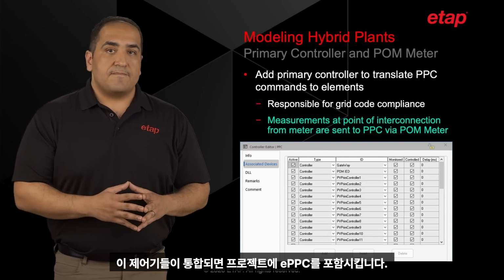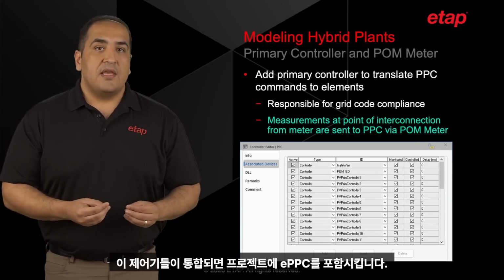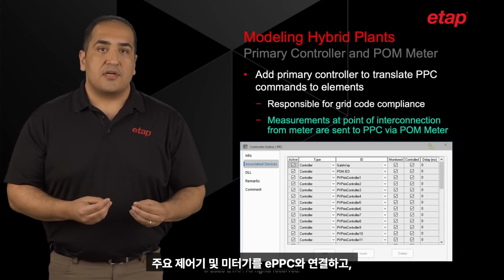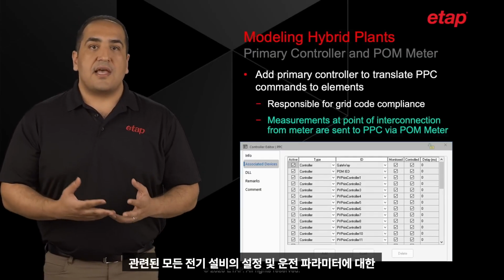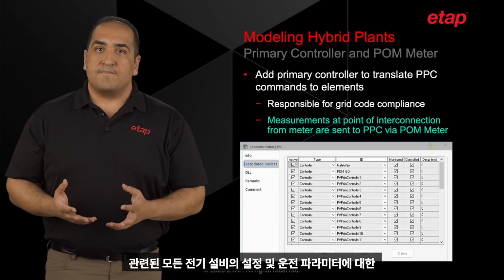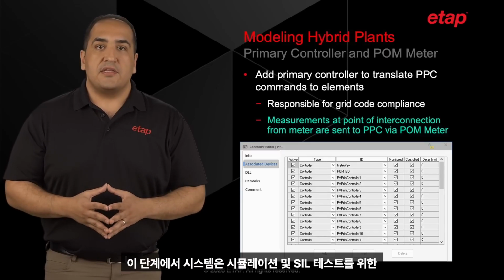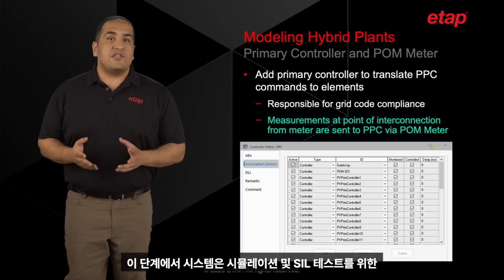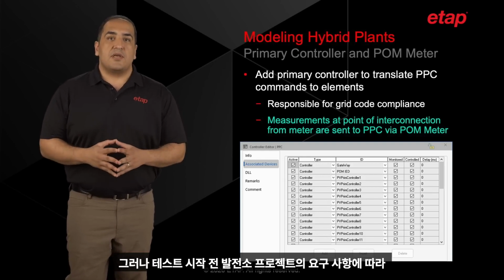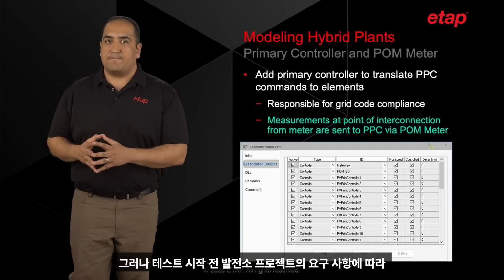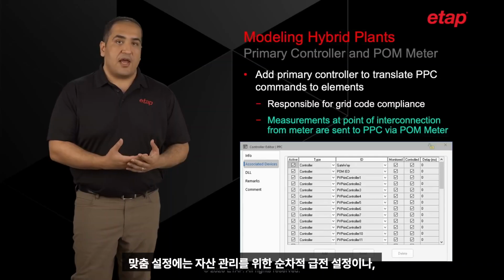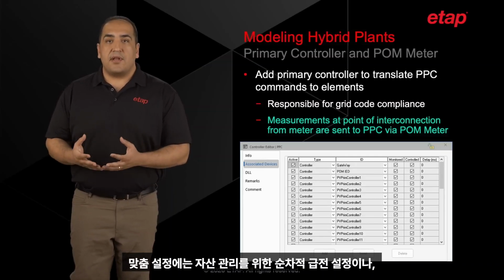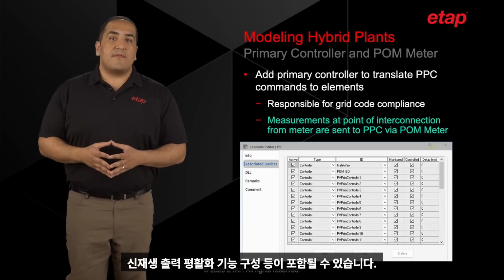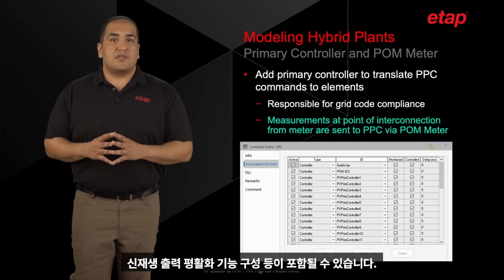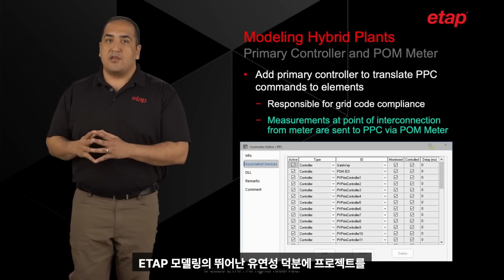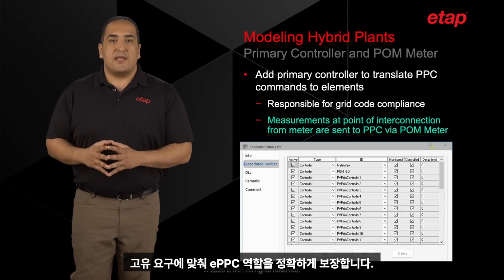Once these controllers are integrated, the next step is to incorporate ePPC into the project. This involves associating the primary and meter controllers with the ePPC and granting it access to the settings and operational parameters of all relevant electrical components. At this stage, the system is nearly ready for simulation and software-in-the-loop testing. However, before initiating these tests, the settings within the ePPC need to be configured according to the specific requirements of the power plant project. This customization could involve setting up sequential dispatch for asset management in one project or configuring renewable smoothing function in another. The flexibility and depth of ETAP modeling capabilities makes it possible to tailor each project to its unique operational needs, ensuring that ePPC can perform its role with precision and efficiency.